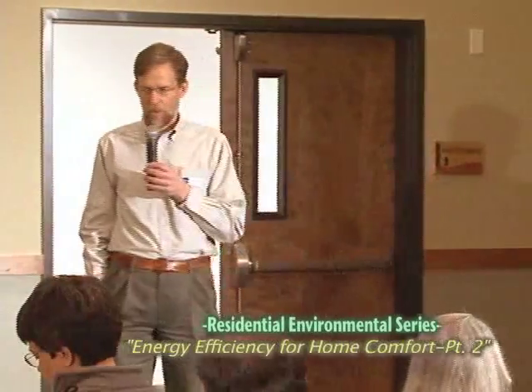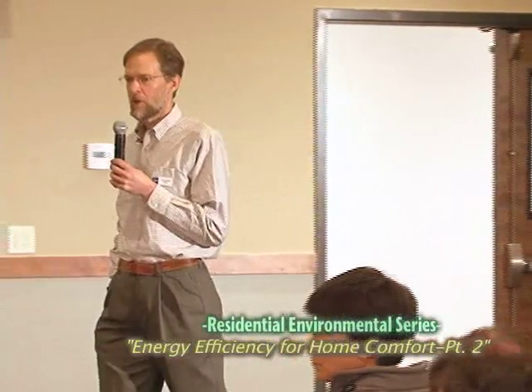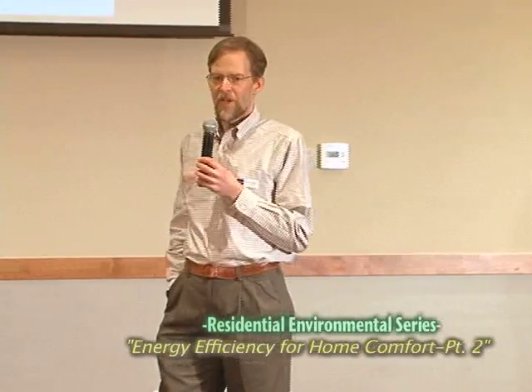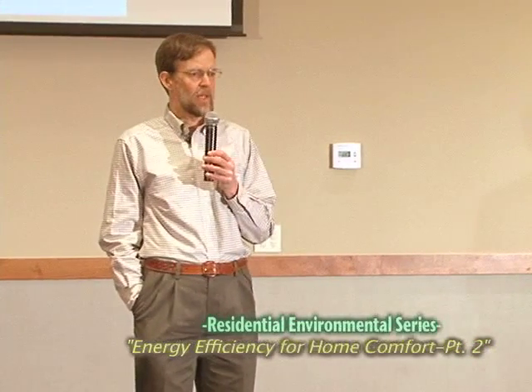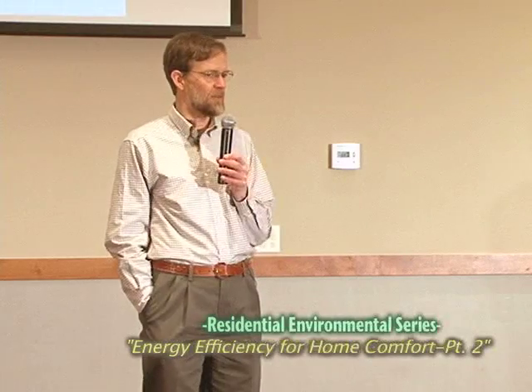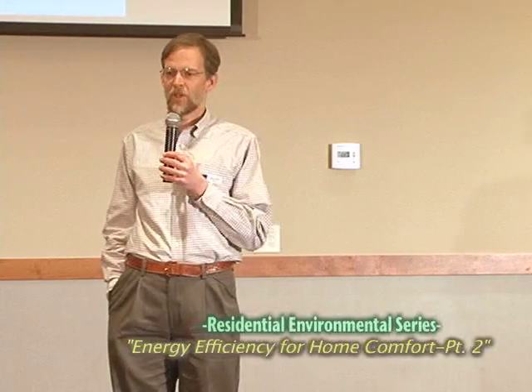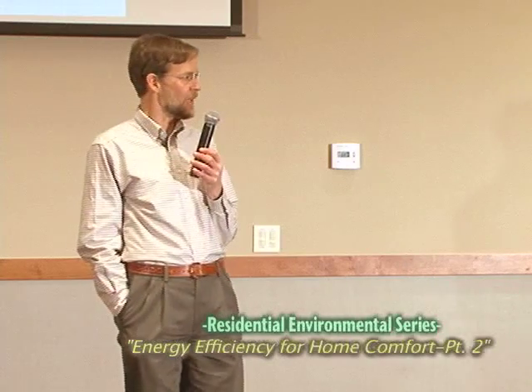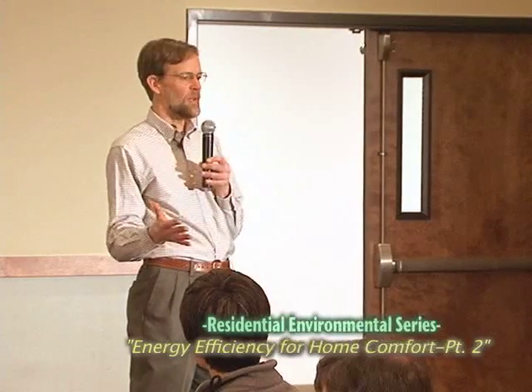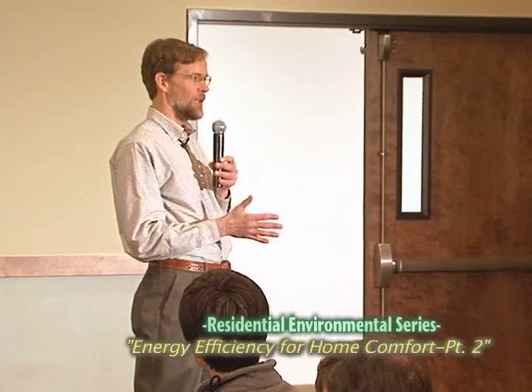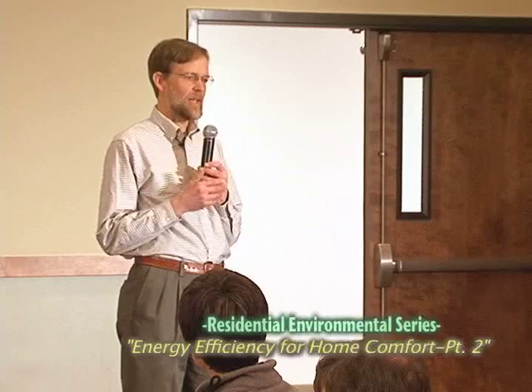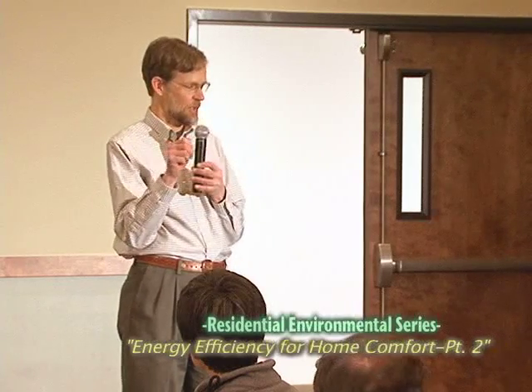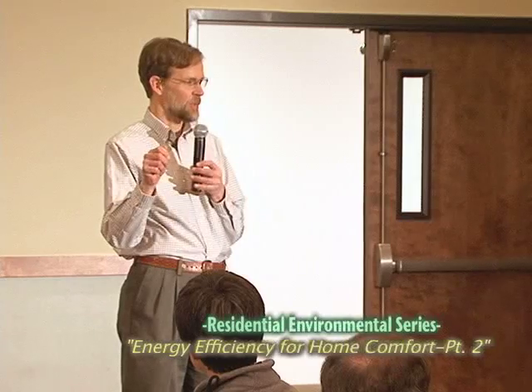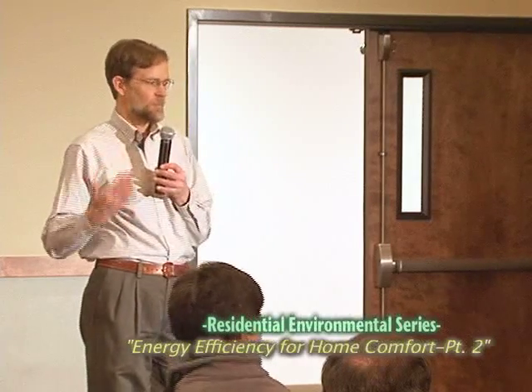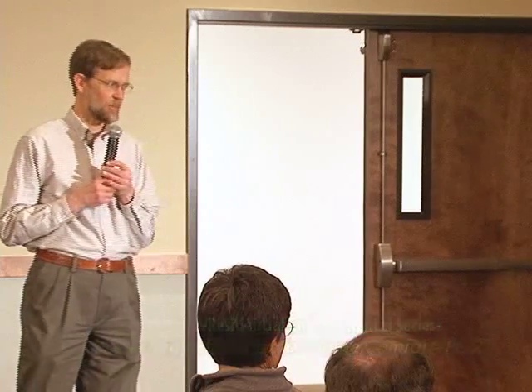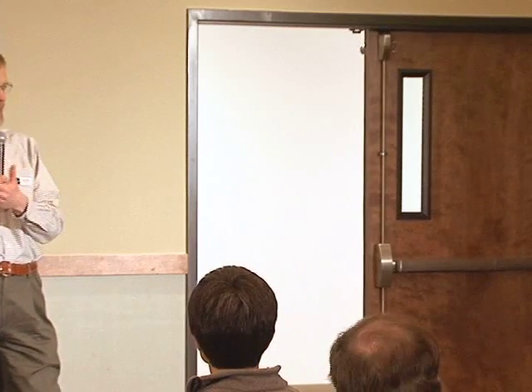Okay, the question is high efficiency blower motors. Is there any rule of thumb about when to replace your blower motor for higher efficiency versus replacing the furnace as a whole with a higher efficiency unit that has a higher efficiency motor? The best application for a high efficiency motor is in applications where the motor runs a lot. So if you're one of these people who has your thermostat fan switch set to on instead of auto, so it's running 24/7, you're running a lot of hours, and that's when you're going to get the best payback on that higher efficiency motor.